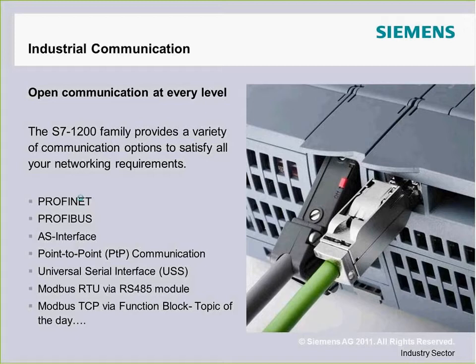There's also some expansion capabilities on the 1200, including Profibus. There's an AS-Interface module, which is kind of a neat power-end communication network for push buttons and actuators and that kind of stuff. There's serial modules available. In fact, one of the major applications that we see with Modbus is that we have a lot of Modbus serial still out there. And with the 1200, we can add a serial module and talk to all the Modbus RTUs, as they're called, and put those up on Ethernet using the built-in Ethernet port and Modbus TCP compatibility. So a neat option for us. Bridge modules and so forth that are available commercially are usually much more expensive than buying the PLC and a serial card. We'll also talk a little bit about functions and how we actually integrate these different protocols into the PLC itself.